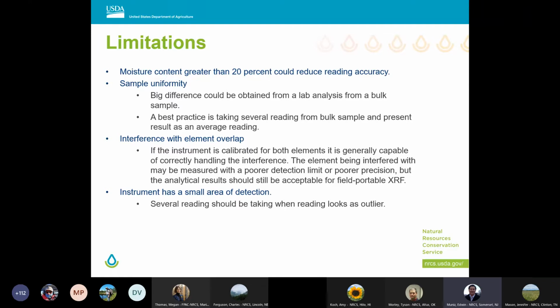There is some interference or some overlaps with other elements. There are some elements whose fluorescence is close. Some of them, for example, will be lead and arsenic. So if you do a right calibration with the equipment, that limitation can be overcome. But if you don't do a good calibration with the equipment, you can have poor precision. So that is something also to keep in mind.